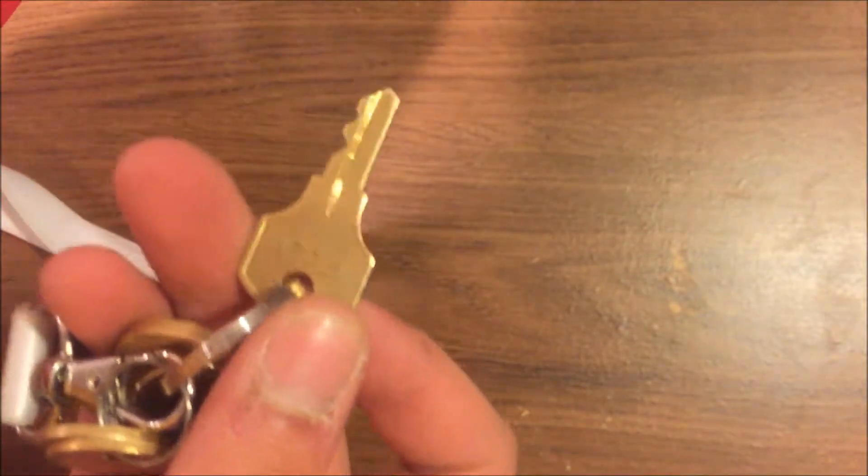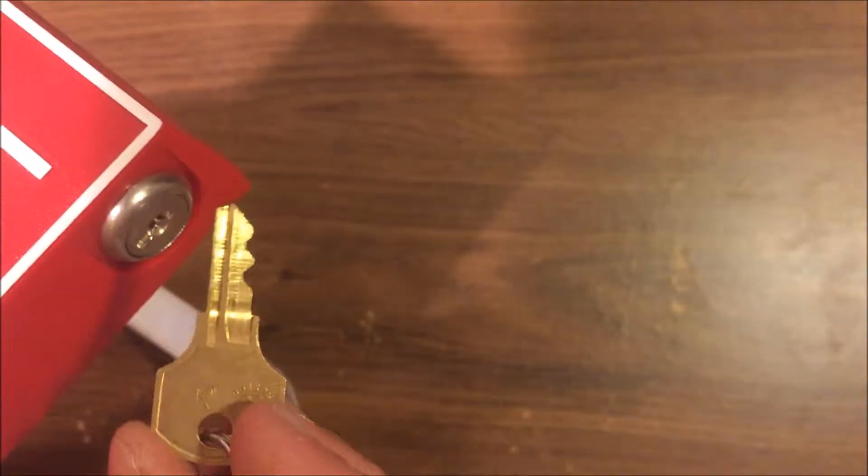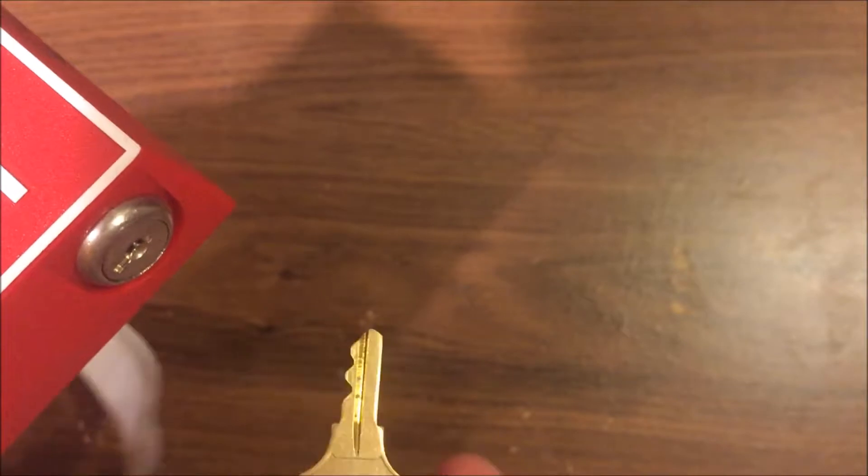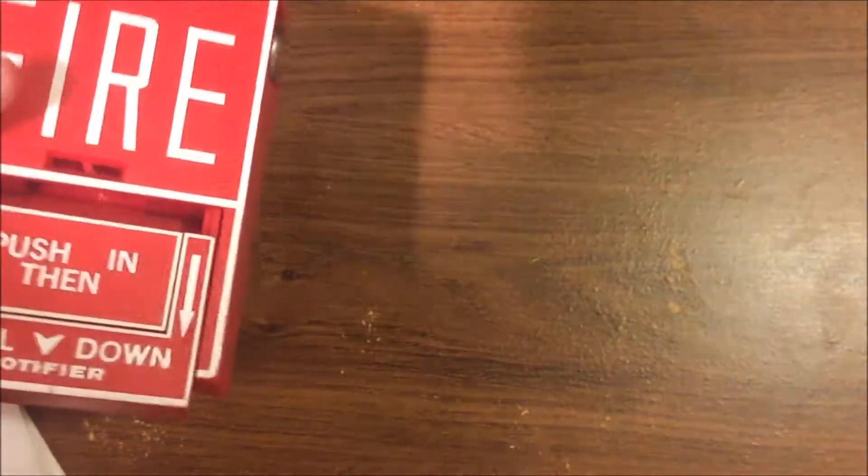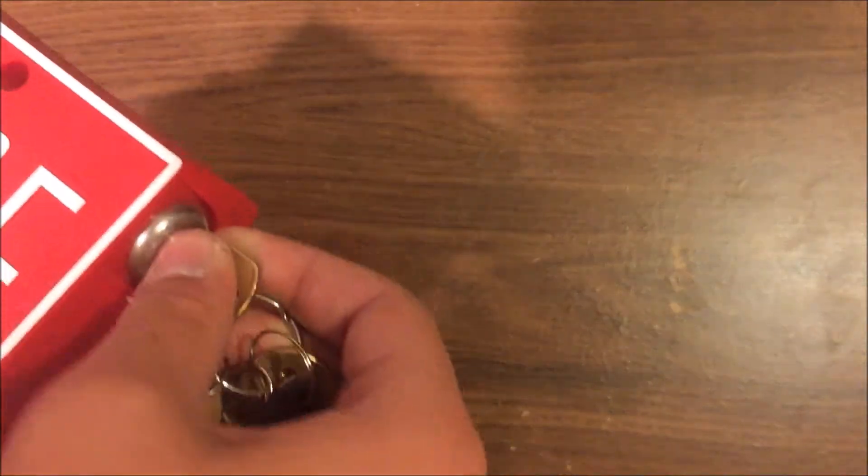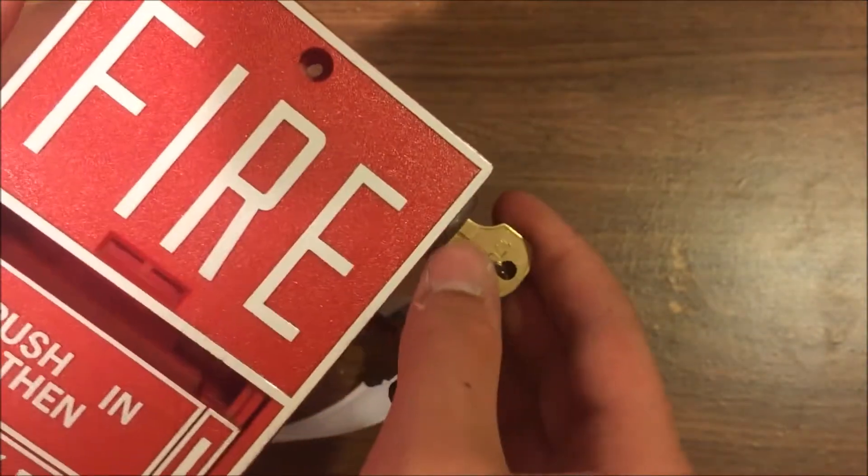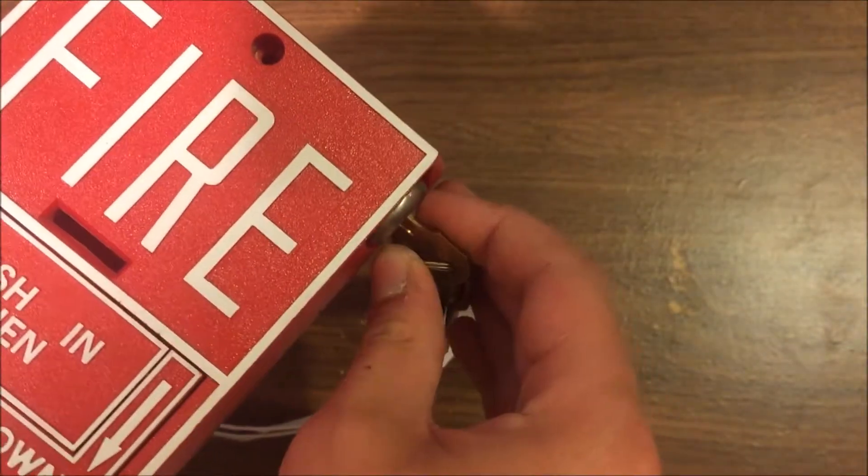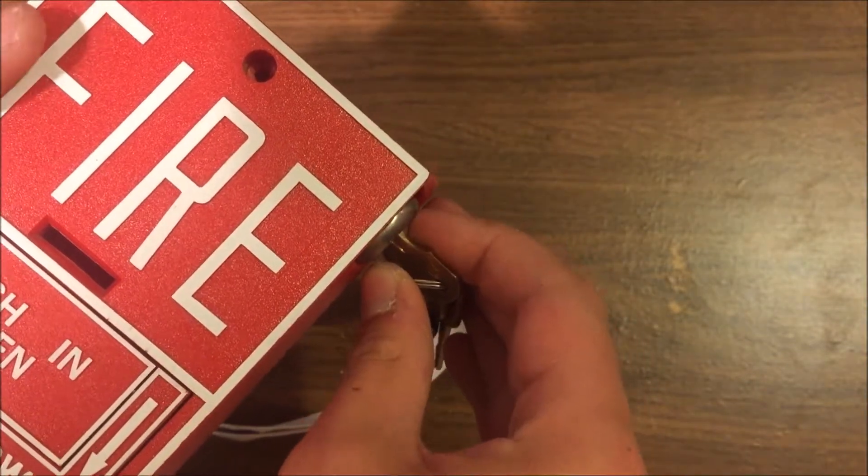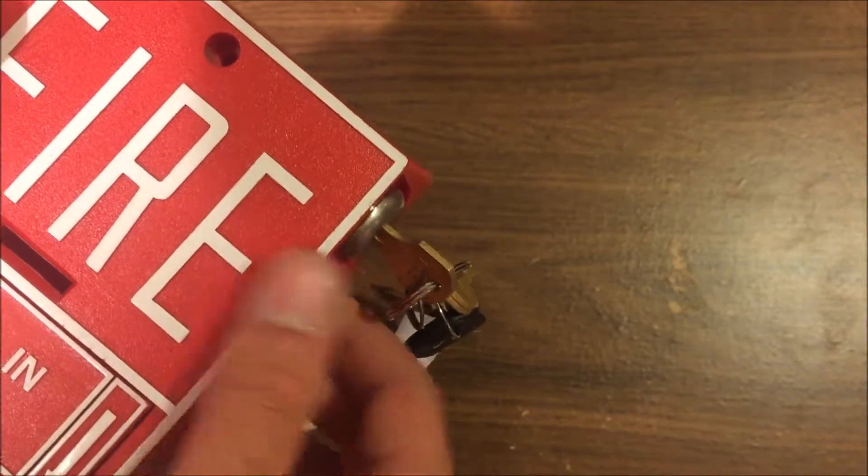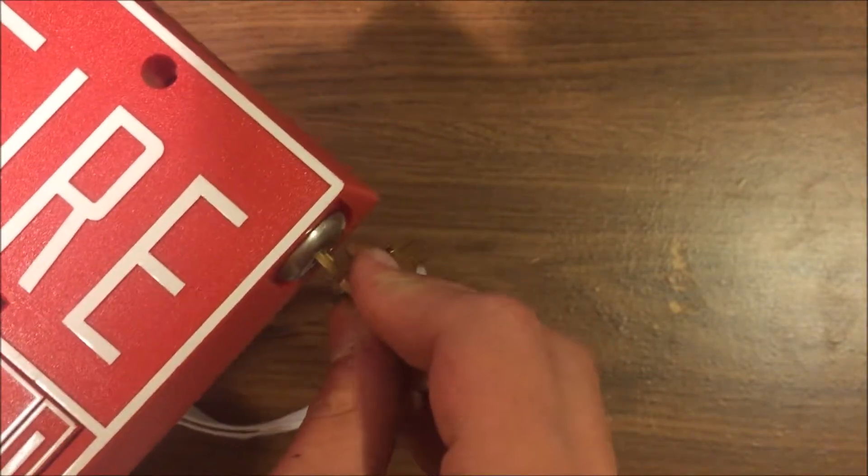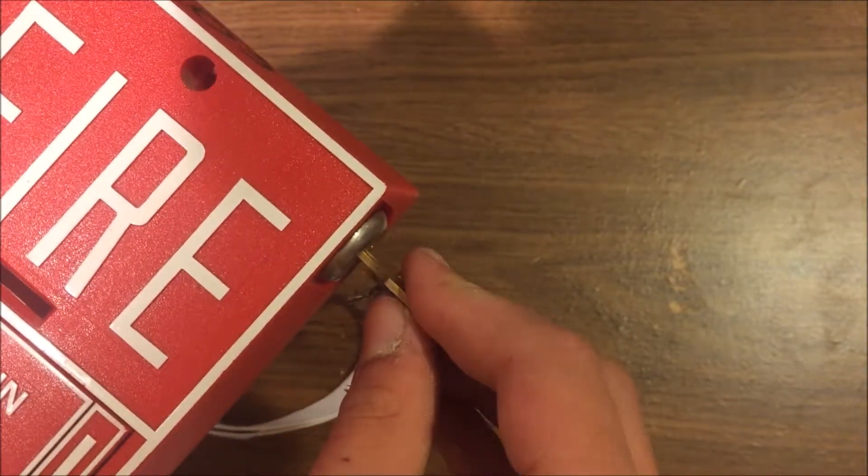I have this key made custom because the pull station didn't come with the key. To reset it, put your key in and turn, and it will spring open just a little bit. That will reset it, and then you just push it back closed and lock it.